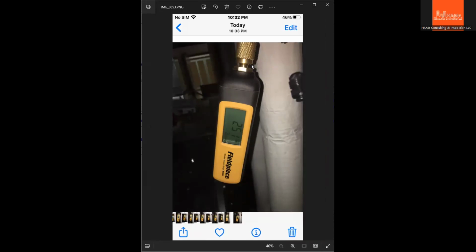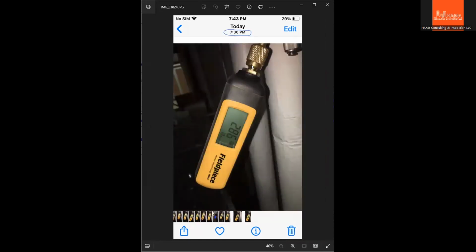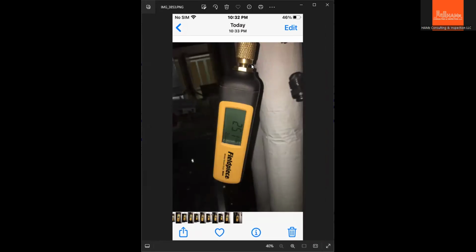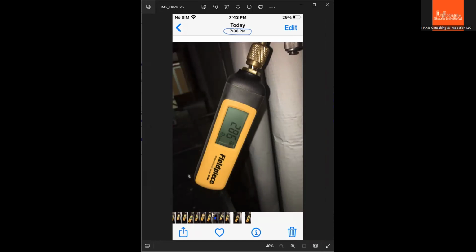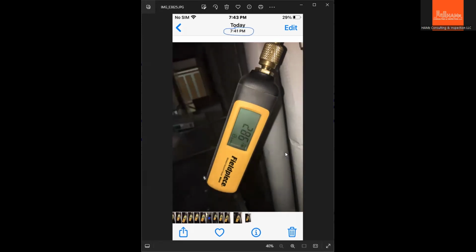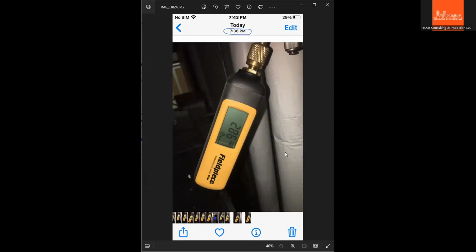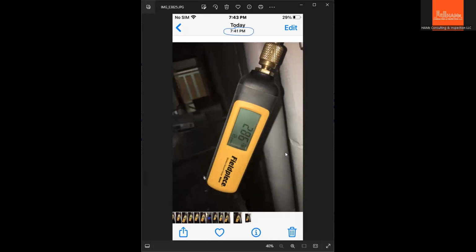In this case, when I took a photo again, the pressure rises, which means there is some leak inside the pipe, the refrigerant piping. So it's a vacuum test. In this case, I think this is a pass under the 500 micron requirement. At 736 to 743, I circled it right here. 7 minutes pass and the pressure still holds. So I believe this is the main requirement: it will hold at a certain point that you need to comply with. A screenshot at 743, and then okay.